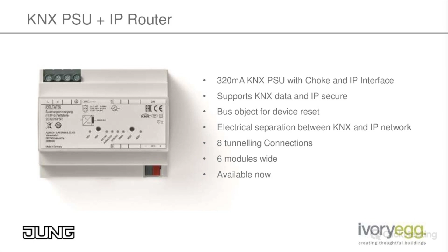Supports KNX data for the objects. There's objects to reset the bus, for example, but also supports IP secure on the IP layer. There's full electrical separation from the KNX power supply and the IP device internally, which is good. And it supports 8 tunneling connections, so you can connect 8 different systems into the KNX. That could be an external AV system like Savant or Control4, or you could be using it for programming. It's 6 modules wide, and it's already available, which is pretty cool.